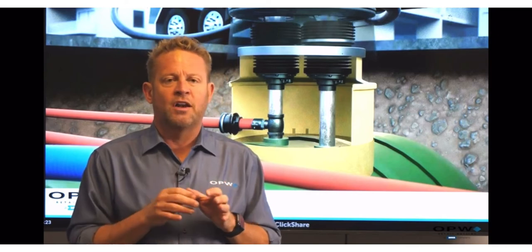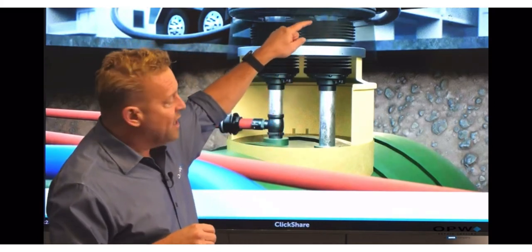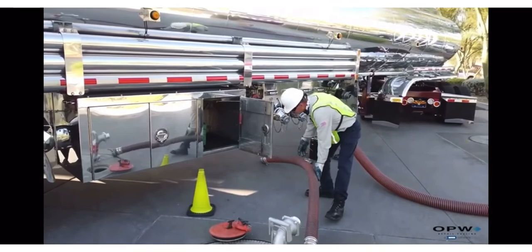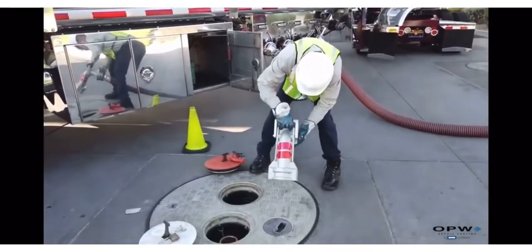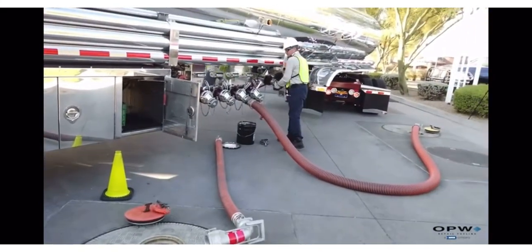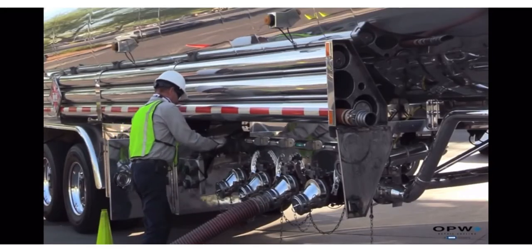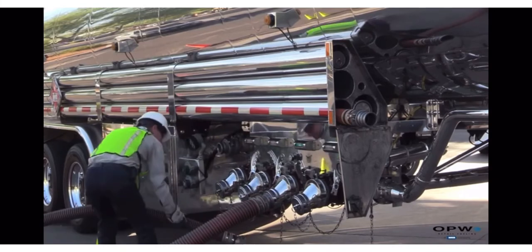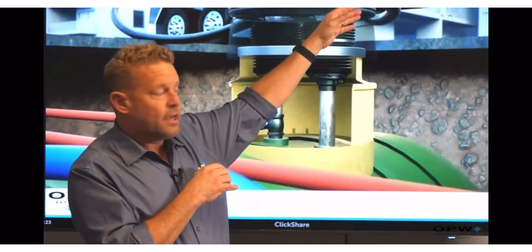What we came up with is what's referred to as stage one or phase one vapor recovery. So now what happens is as fuel is dropped into the tank, before the driver makes that drop he has another hose on his truck. It's referred to as a vapor recovery hose. It's usually orange. They try and separate the two. It's usually a bit smaller diameter, a vapor recovery hose usually three inch.